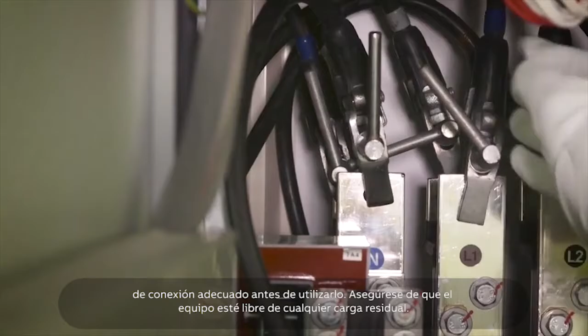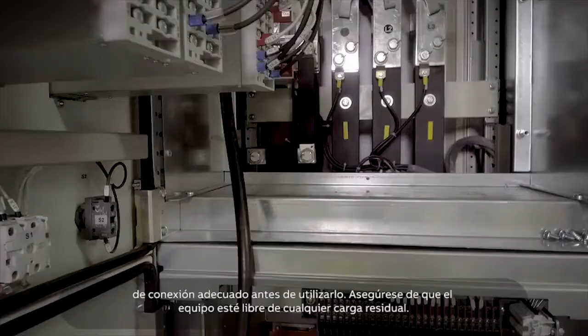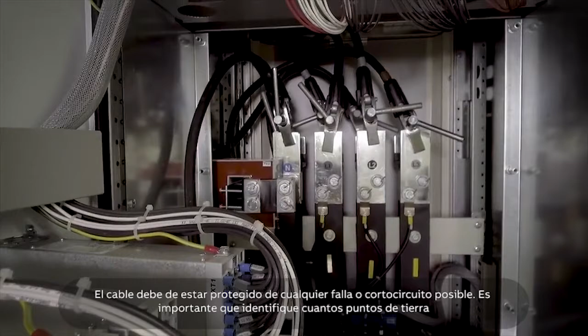conductors. By applying your own local or personal earths, you shall ensure that the equipment is free of any residual charge, induced voltages, and protected from any potential short-circuit fault current. It is highly important that you identify how many sets of earths have been applied on the control document to ensure they're all removed before energizing the circuit.